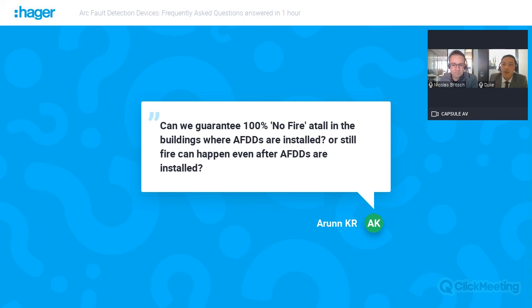I just want to add a quick comment. Indeed, as Nicolas explained, the AFDD is for electrical fire, especially for arc fault protection, as we explained during the webinar. The other faults are still protected by MCBs, RCDs, etc. One comment about the 100% mentioned in the question: we follow the product standard IEC 62606 strictly with all the type tests. We test with different types of arc faults, and we have the endurance test as well, to test the reliability of the algorithm and the product, and of course we pass and are certified. So on that we have a good proof.